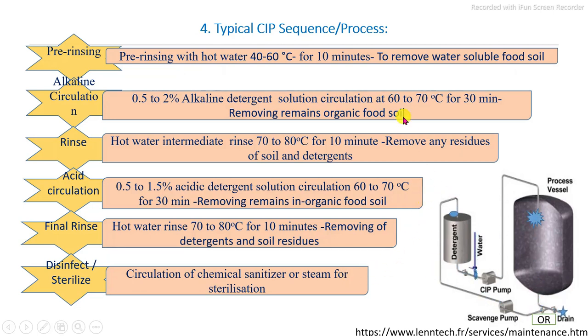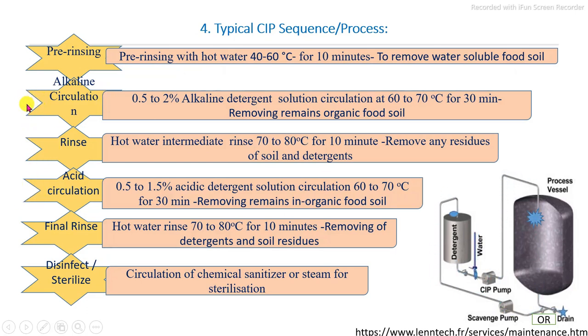In this typical CIP sequence, all processing equipment follows this sequence, which is carried out depending on the specific application. For example, in some processing industries acid circulation is carried out between the intermediate rinse and the disinfection stage as per requirement. However, pre-rinsing, alkaline cleaning, and final rinsing are the main basic steps of the CIP sequence. You can see in this picture how detergents and water are circulated through the processing vessel for cleaning.